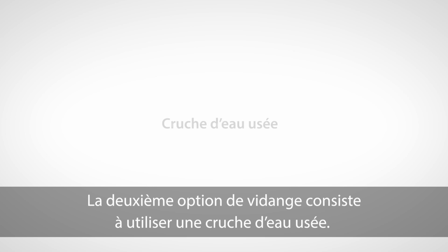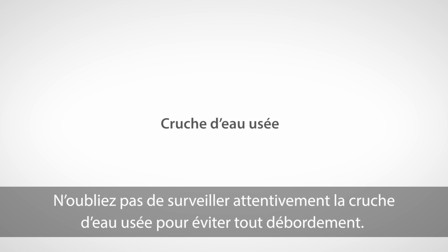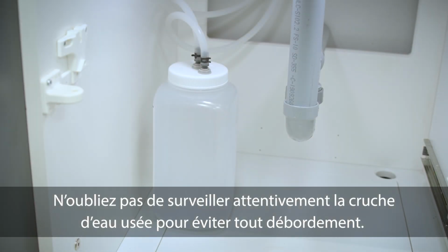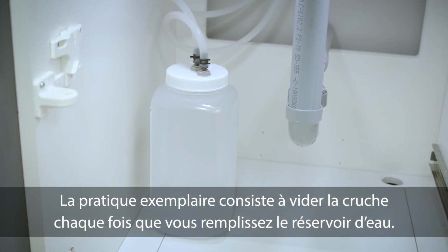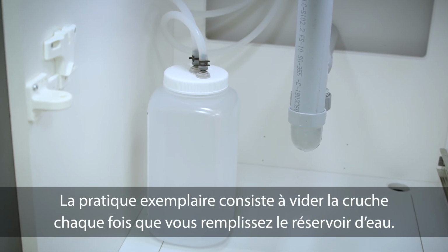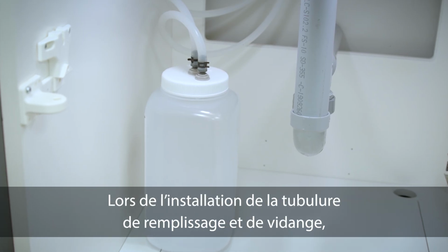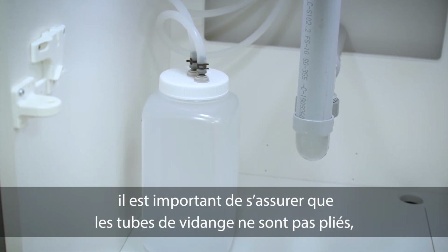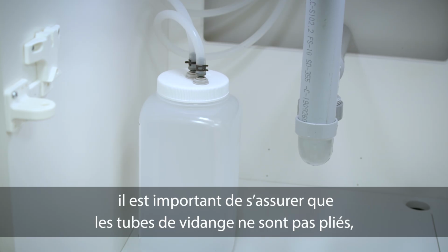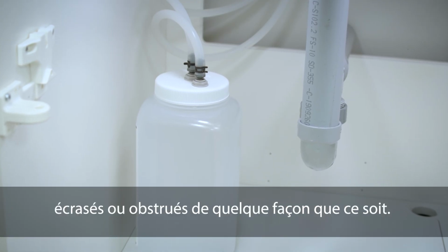The second drainage option is to use a waste bottle. Remember to carefully monitor the waste bottle to avoid overflow. The best practice is to empty the bottle every time you refill the water reservoir. When setting up the filling and drainage tubing, it is important to make sure the drainage tubes are not bent, crushed, or obstructed in any way.